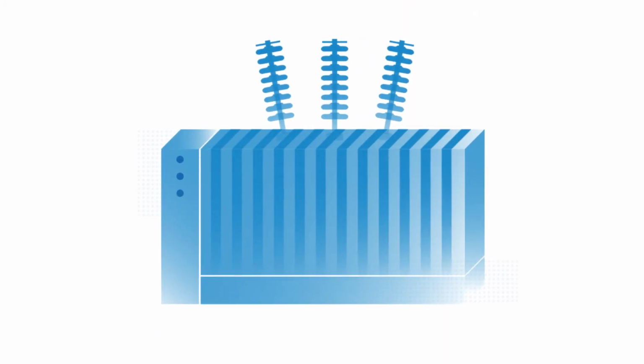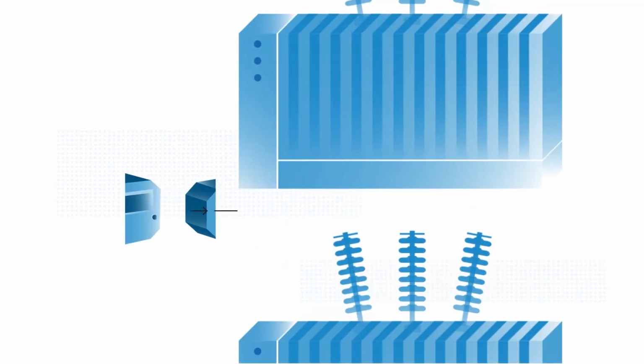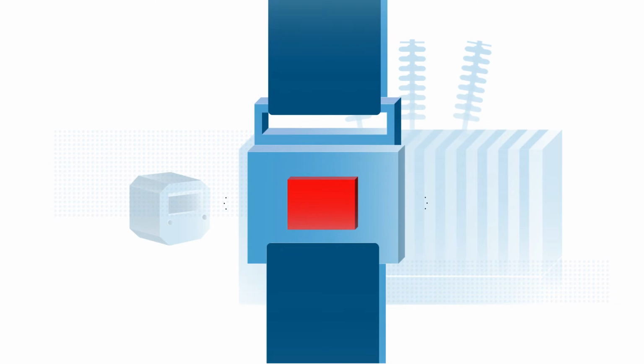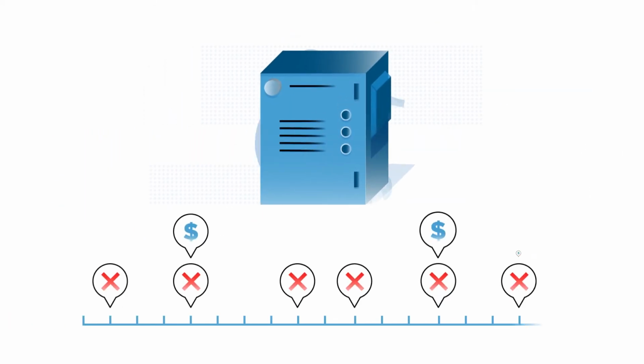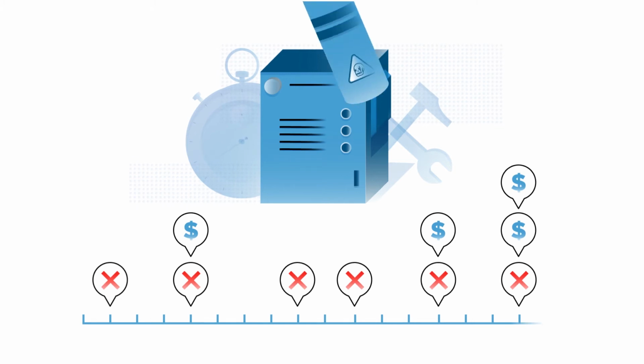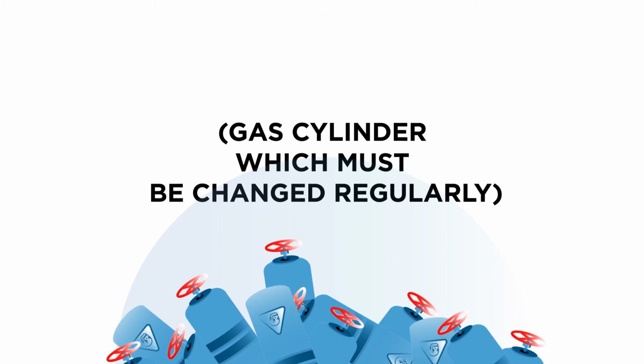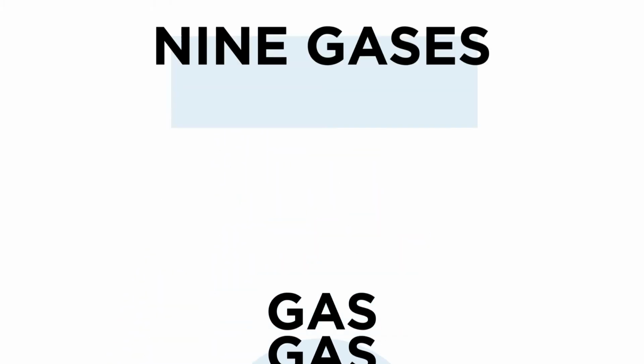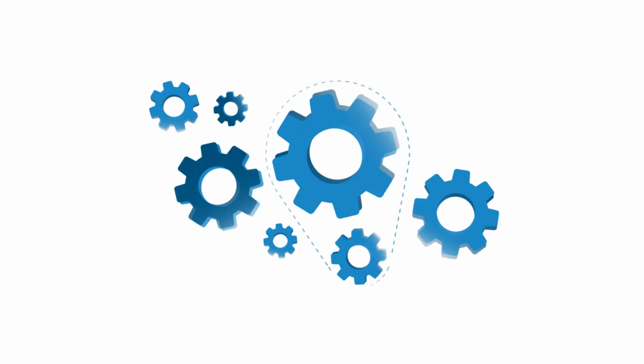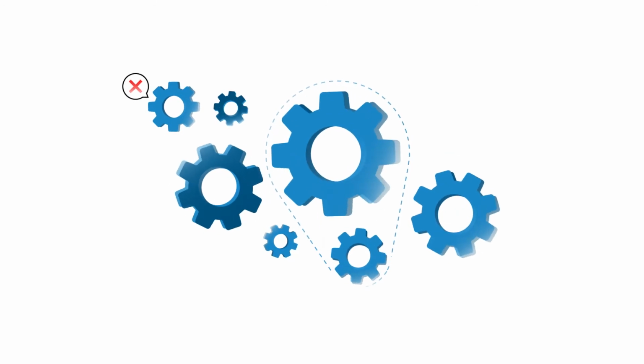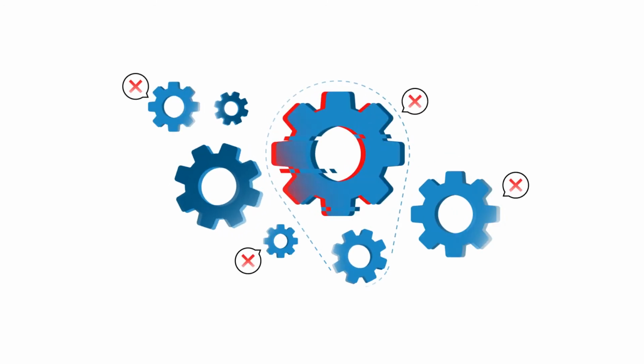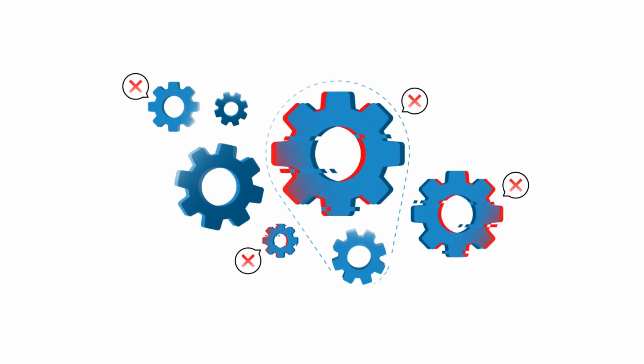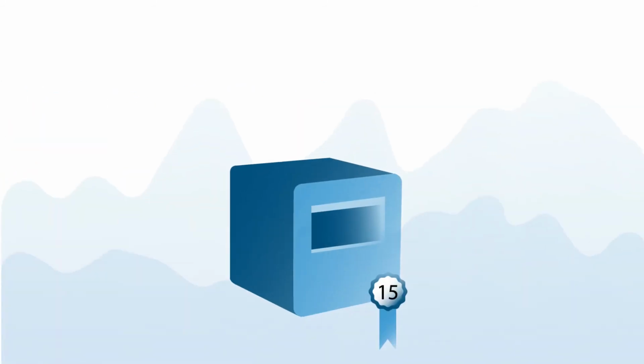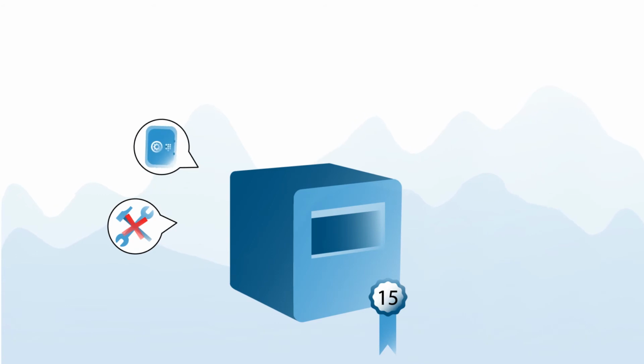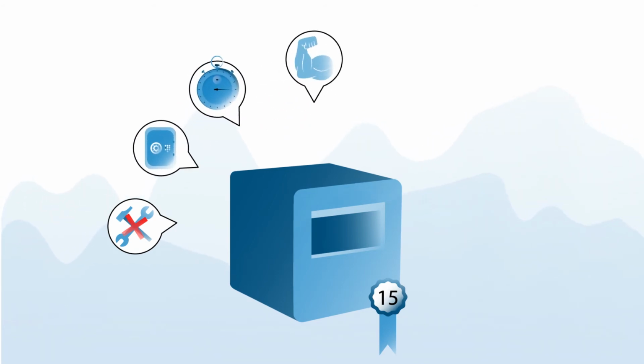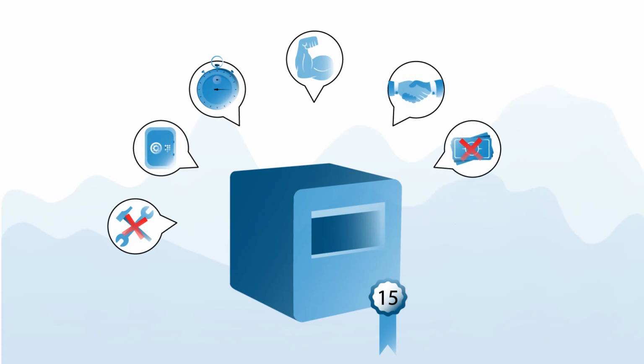MTE HYDROCAL devices are capable of being transported and can be easily installed on other transformers without a huge effort from the user. Some systems need regular maintenance for the extraction system or for the measurement of gases, or even recalibration during operation, thereby requiring the use of carrier gases. Multi-gas systems that can measure up to 9 gases and moisture individually are generally very complex technologically and often combine many moving components, and therefore have the disadvantages of a high potential risk of failure in comparison to systems using fewer moving parts. The challenge of MTE is now to design online monitoring systems that meet the high requirements of our customers, which means they can be connected to transformers for many years with the highest reliability.